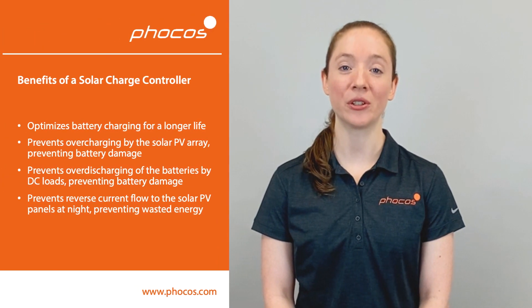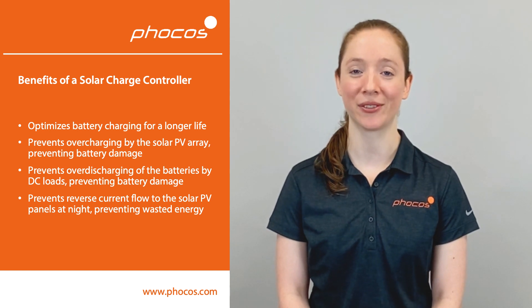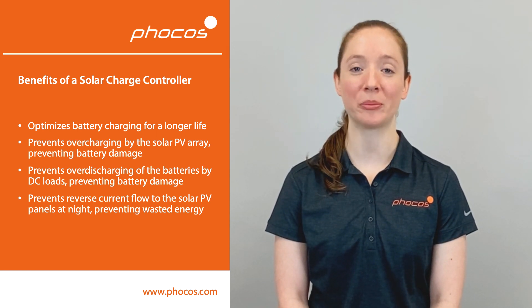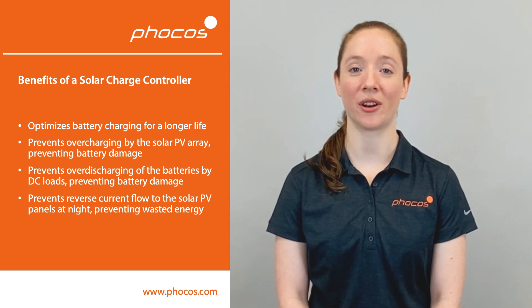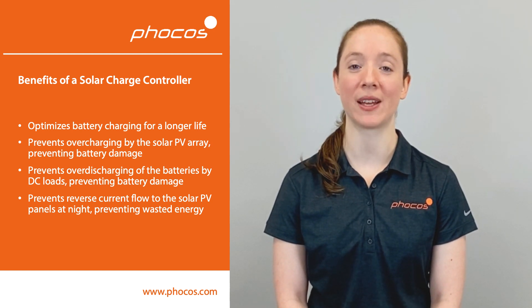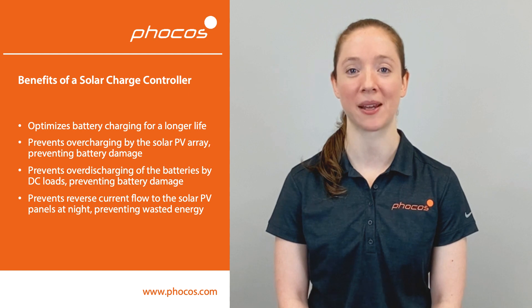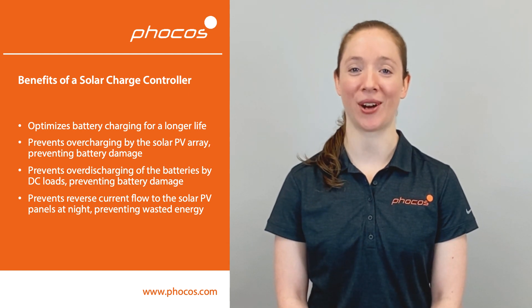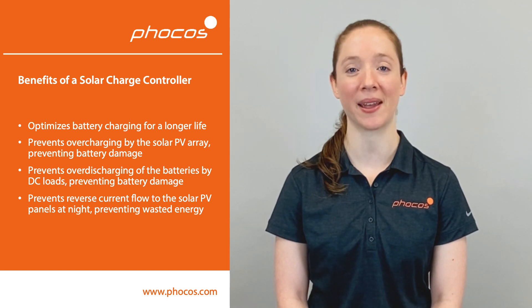A solar charge controller optimizes battery charging for longer life. It prevents overcharging by the solar PV array, preventing battery damage. It also prevents over-discharging of the batteries by DC loads, which also protects the battery from damage. Phocos solar charge controllers also prevent reverse current flow to the solar PV panels at night, preventing wasted energy.